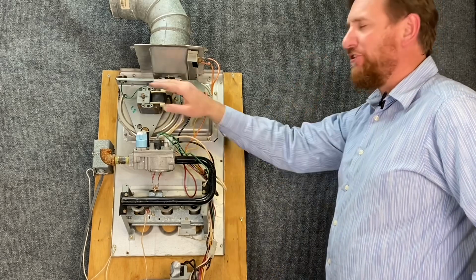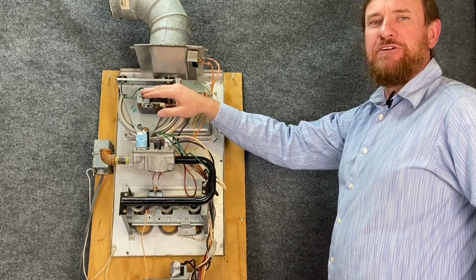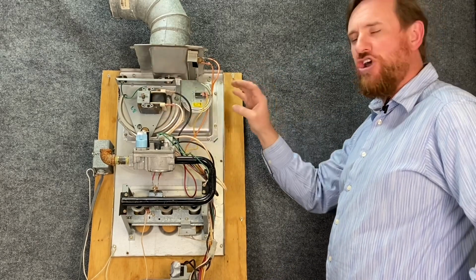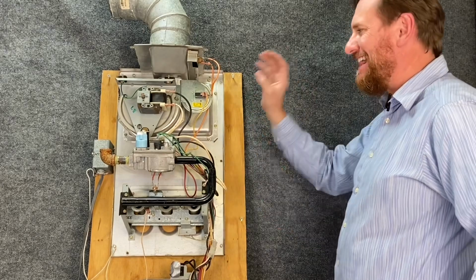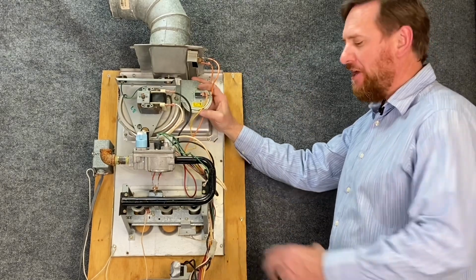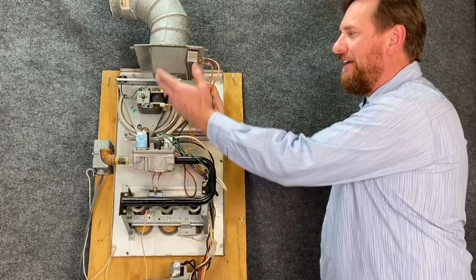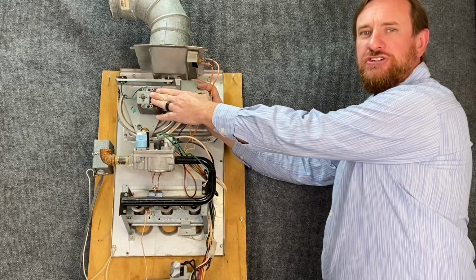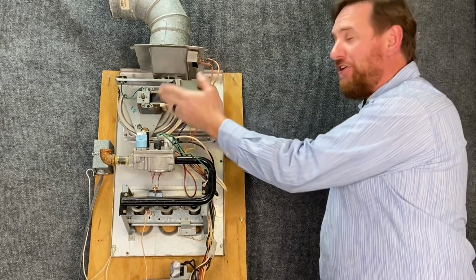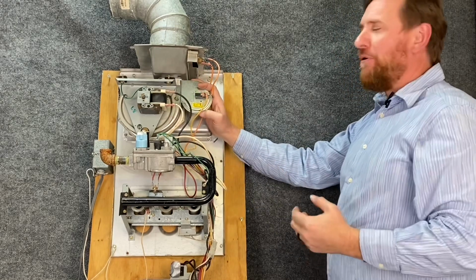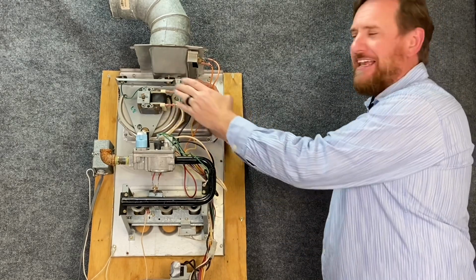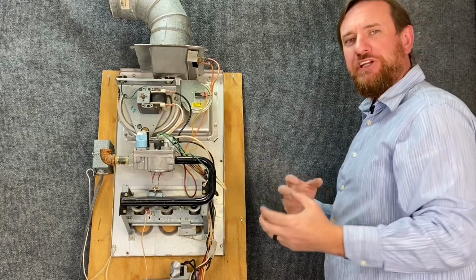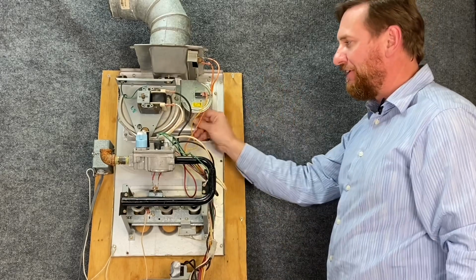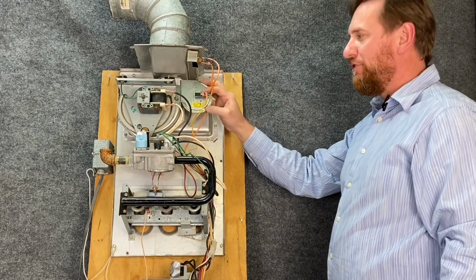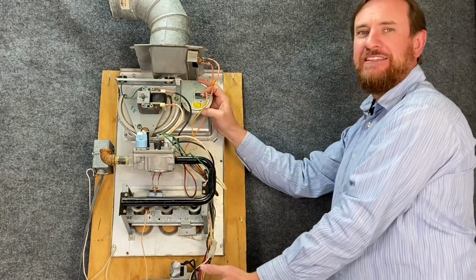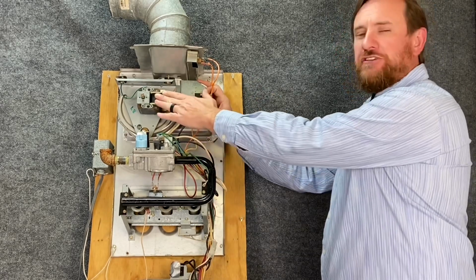It's essential that we have this motor working, and we don't just want to assume that it's working. We need to know without a shadow of a doubt it's working, and that's why our pressure switch comes into place. Our control board just closes the relay and sends the voltage to this inducer fan motor, but it doesn't know if it's doing its job. What we have here is our vacuum pressure switch. As this motor's running, pulling a draft through the heat exchanger, it's also pulling a vacuum to the switch. The switch closes, 24 volts goes back to the IFC. We know for sure that this motor is working.